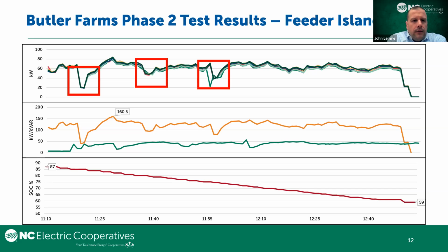You can see here in these boxes the trend of our power output of the microgrid, where we had trips and the system dropped off. The microgrid operates on 400 volts on the secondary side, but that voltage was hard-coded into our control system. It just so happens that this test was done during a really hot period with really high loads, when we were operating in our emergency voltage band. The control system was set to take that absolute 400 volts and then apply plus or minus 10%. But in utility practical operations, during high loads your system may run off of nominal voltage and may run low. And so we were having trips on the microgrid, and we couldn't figure out why.